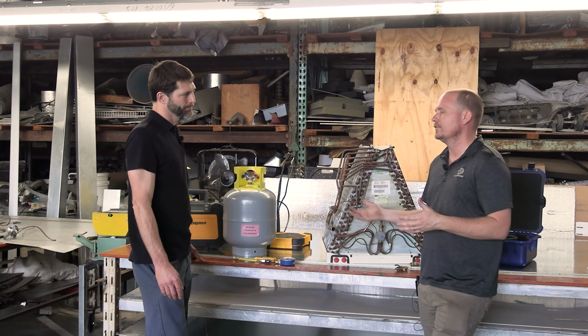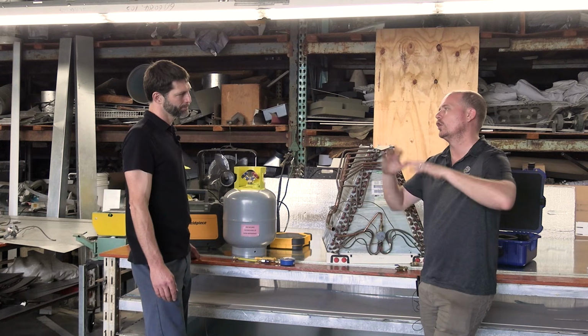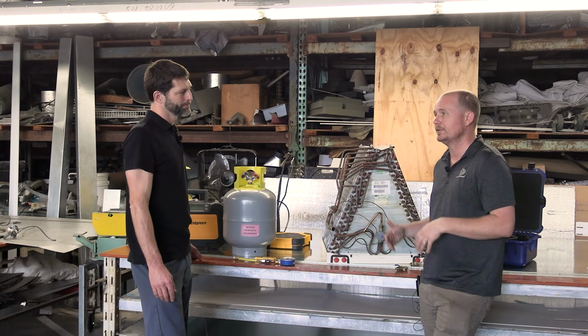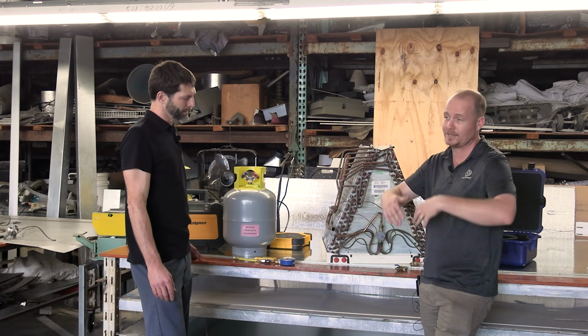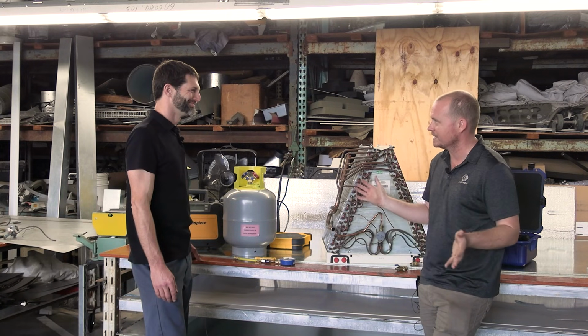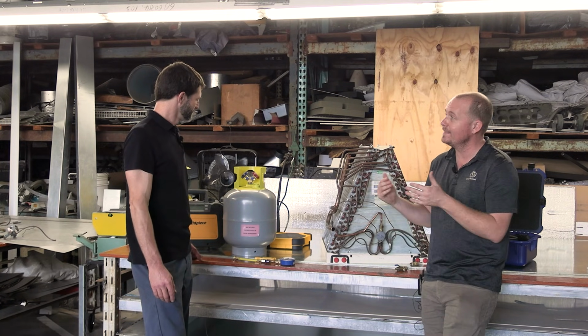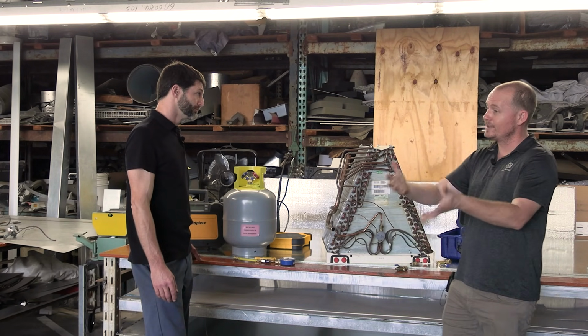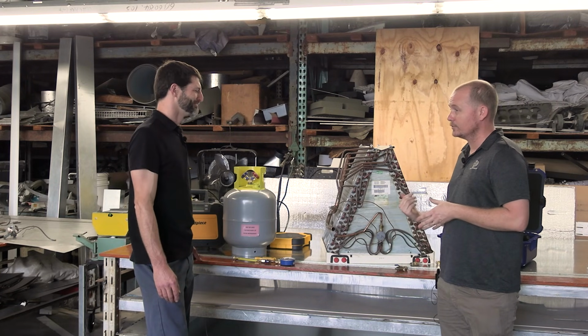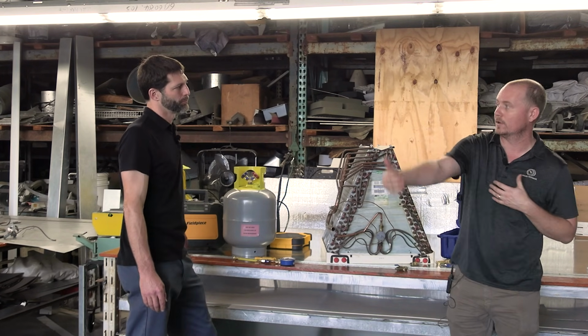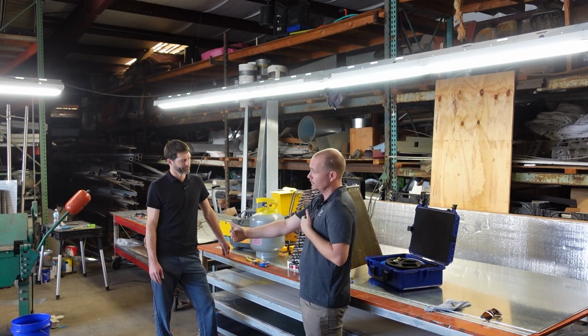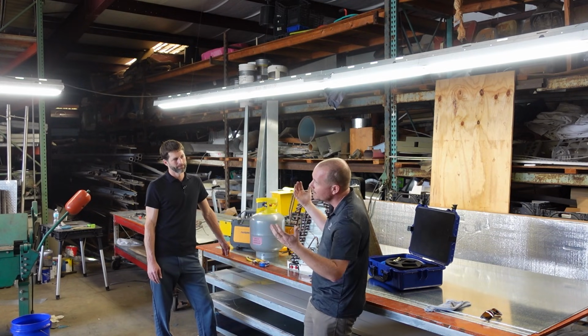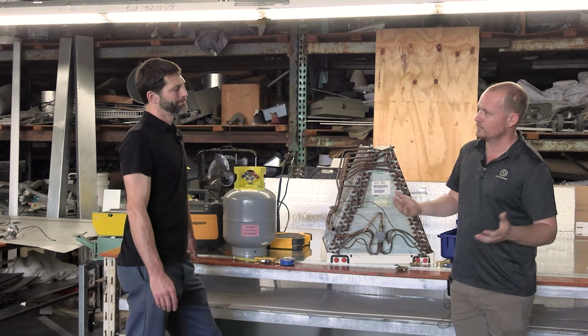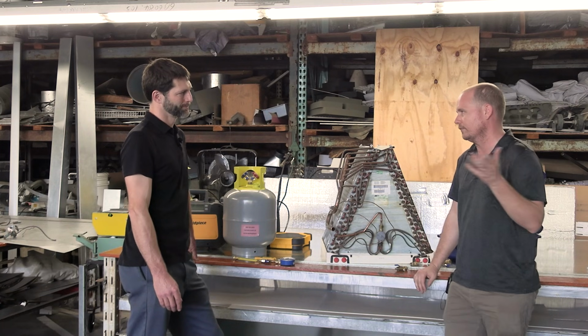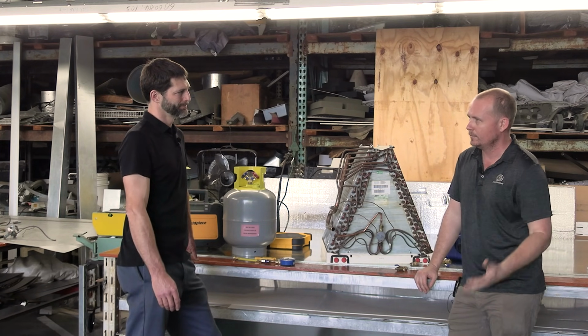Now, let's say there is a case where you have a large amount of refrigerant that you've pulled out of a system and you don't want to waste it and you're going to put it back in because your employer told you to, or whatever the case may be. That happens. In that case, when you take it out, you want to run it through the inline filter dryer, and when you put it back in, you want to run it through an inline filter dryer as well, because at least that gives you protection against solid contaminants and that sort of thing. Certainly not going to dry out wet refrigerant completely, but it can help with keeping it a little bit cleaner.